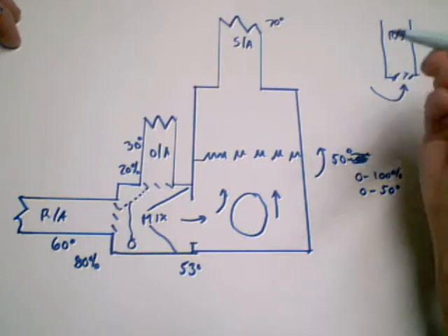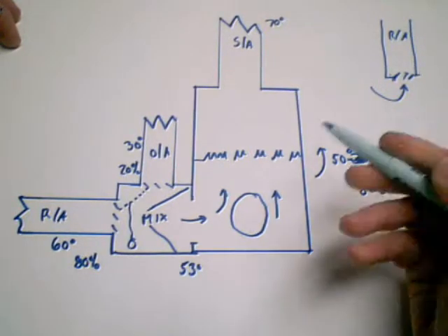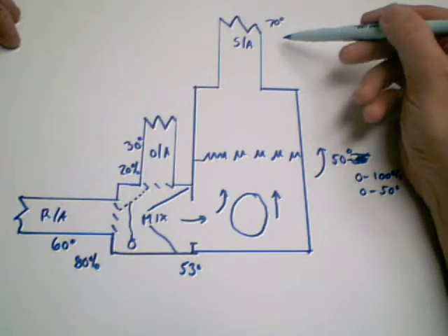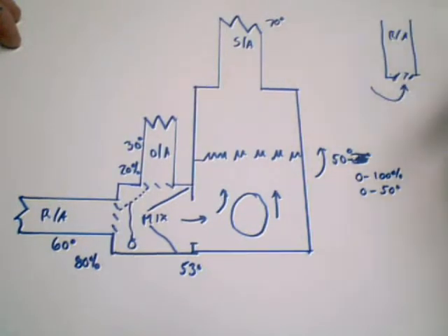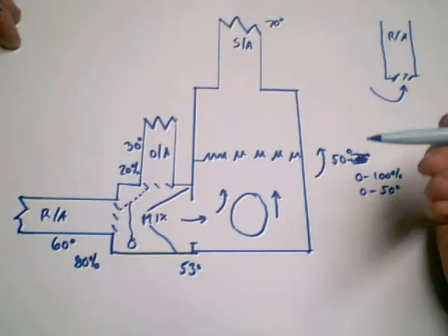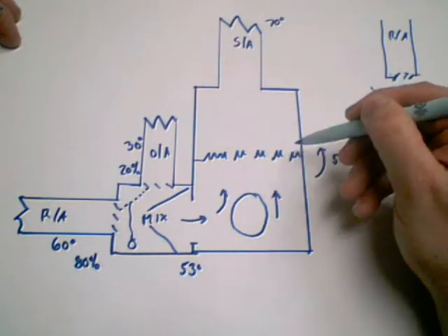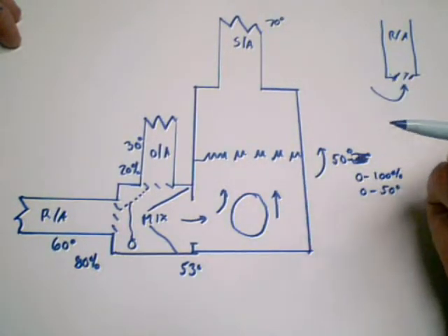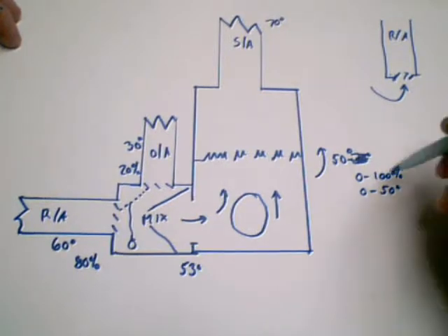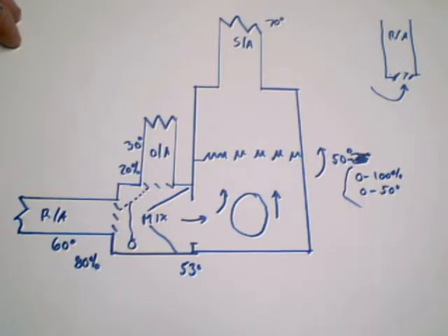and anywhere in between. That's the modulation, so that if we don't necessarily want to have a 103 degree discharge temperature, we can bring that down somewhat and modulate that, both for energy efficiency purposes and, as you'll see here in a little bit, for makeup air purposes. So that's an important part here too, is that flame modulation.